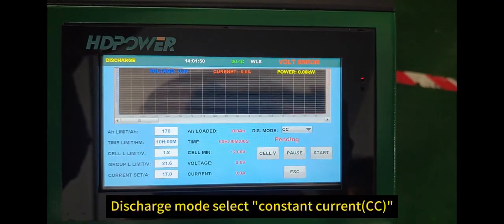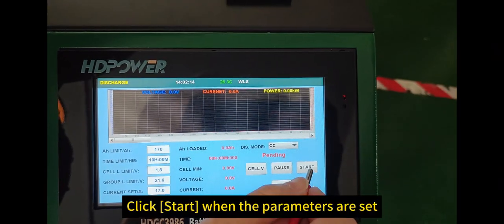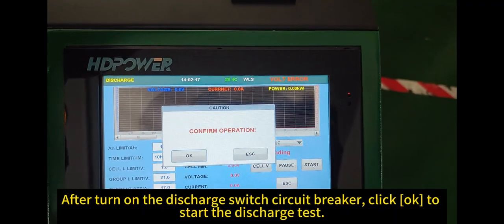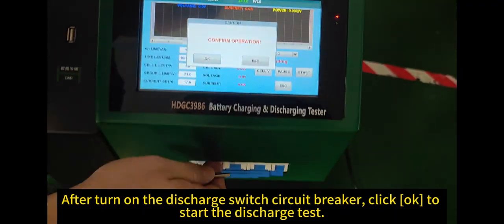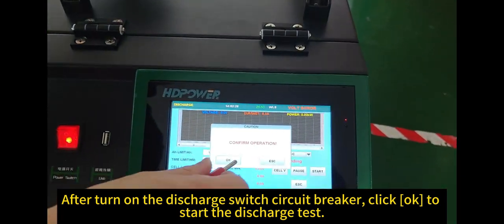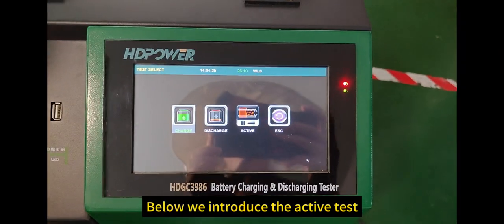Discharge mode select constant current CC. Click Start when the parameters are set. After turn on the discharge switch circuit breaker, click OK to start the discharge test. Below we introduce the active test.